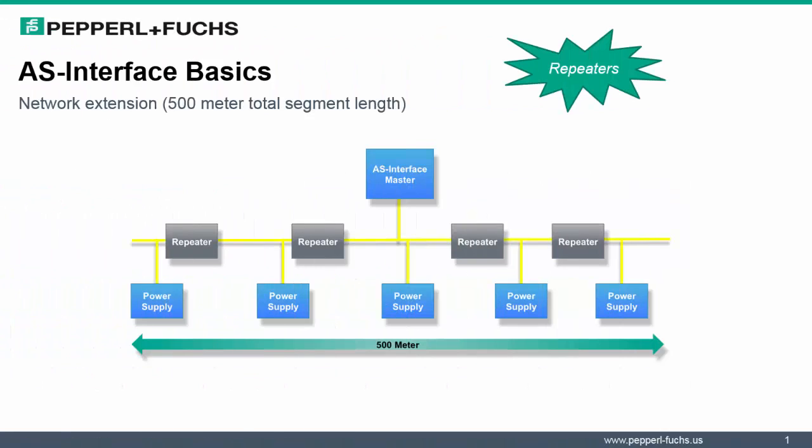Let's look at expanding yet our network further. In the following diagram, we strategically place our AS Interface master in the middle of our network. With the limitation of having two repeaters on each end extending in each direction, we have the ability now to expand our network up to 500 meters. This is a significant value for those networks that require larger, longer lengths.